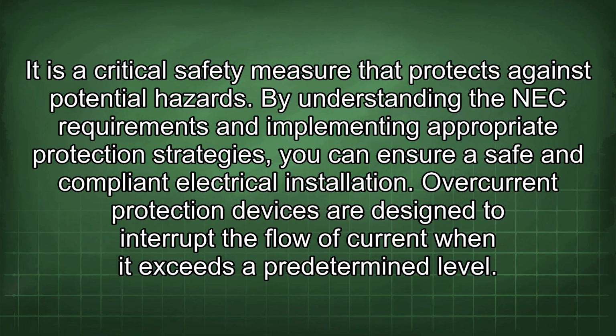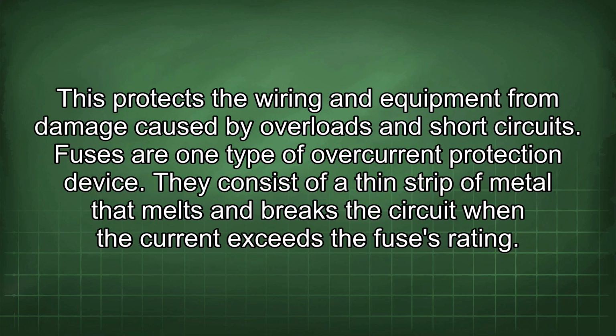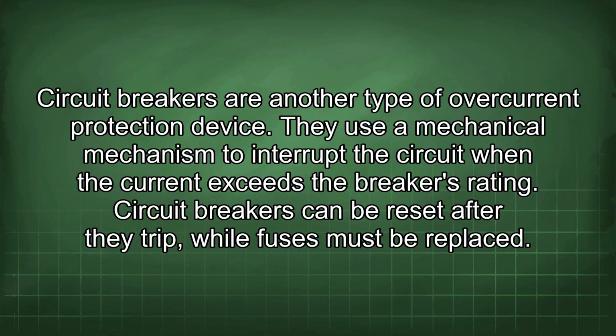Overcurrent protection devices are designed to interrupt the flow of current when it exceeds a predetermined level. This protects the wiring and equipment from damage caused by overloads and short circuits. Fuses are one type of overcurrent protection device. They consist of a thin strip of metal that melts and breaks the circuit when the current exceeds the fuse's rating. Circuit breakers are another type of overcurrent protection device.